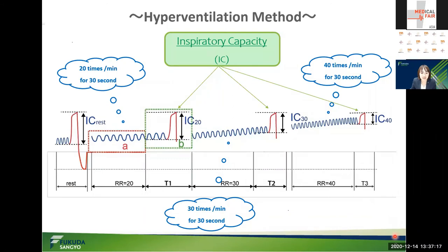Dr. Fujimoto focused on the fact that DLH occurs depending on the respiratory rate. The respiratory rate gradually increases from the resting breath in steps of 20, 30, and 40 breaths per minute, and the inspiratory capacity is measured at each step. By verifying the decrease of inspiratory capacity, he developed a simple and quantitative method to assess DLH. This is the innovative function of our new Spiro Analyzer ST-190: the hyperventilation method.